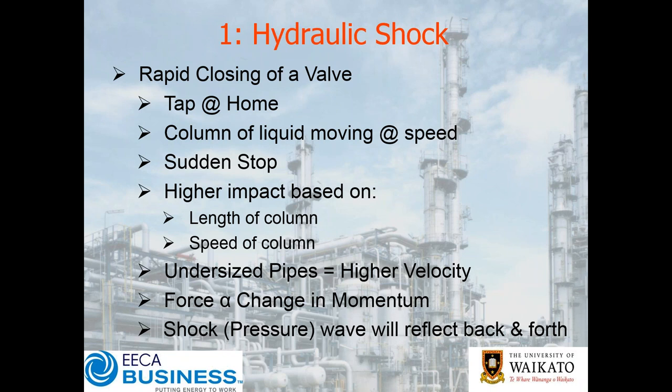What's happening is you've got water flowing down a pipe — a certain mass of liquid moving at speed. When you shut the tap off, if it shuts off really quickly, that moving fluid has got nowhere to go. In a liquid system, water is by and large an incompressible fluid, so it can't compress against the tap. You end up with a pressure pulse that bounces up and down the pipe because there's a sudden change. We get a bigger impact based on the length of the column and the speed of the column.